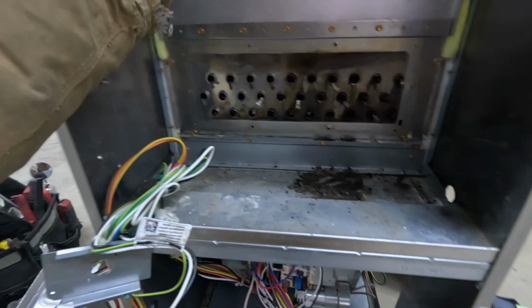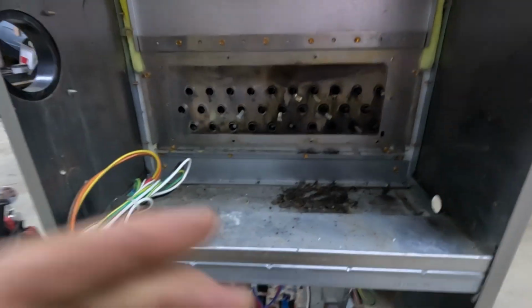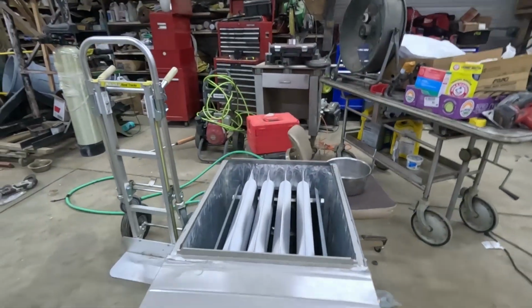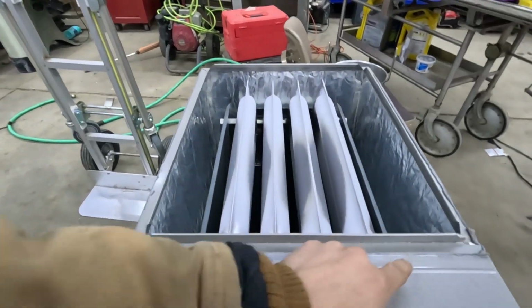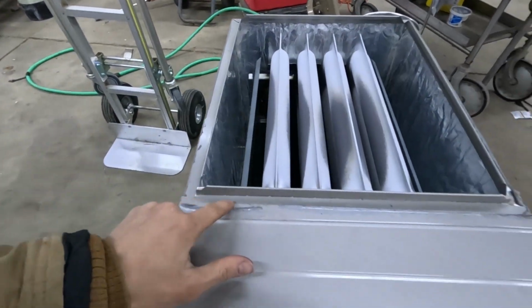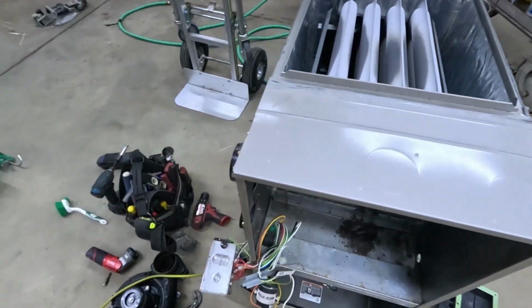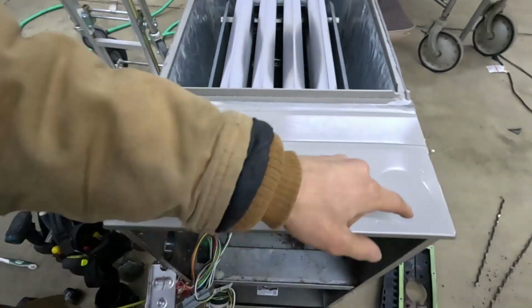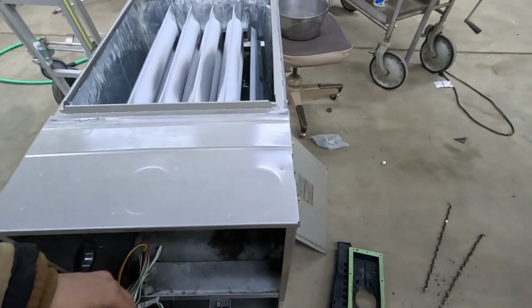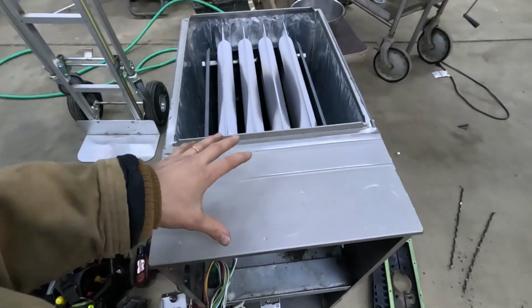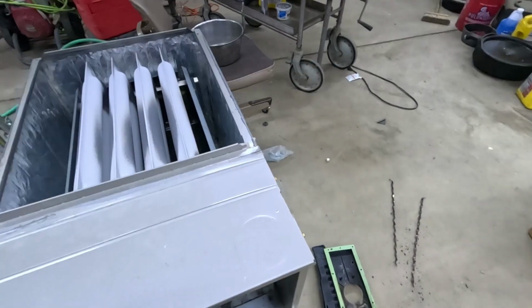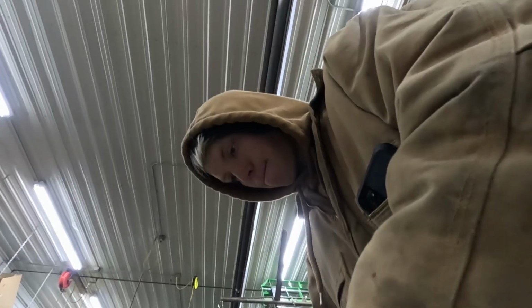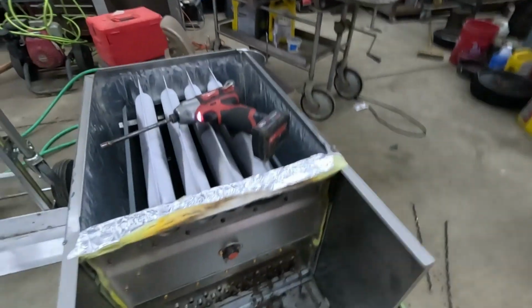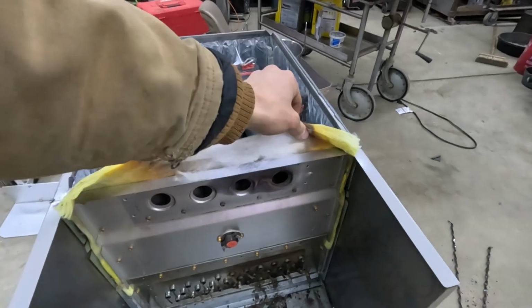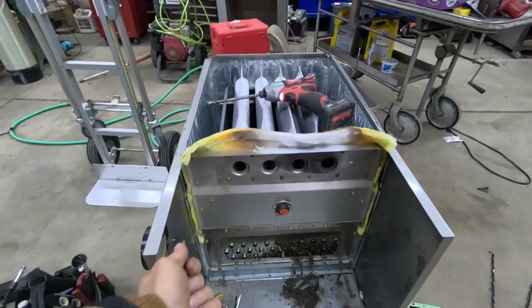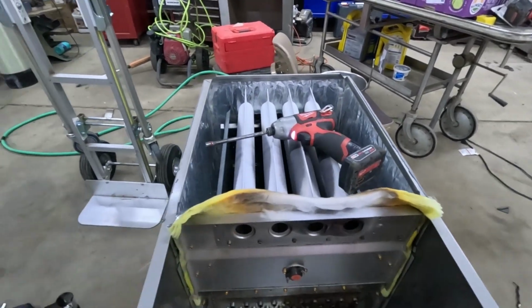We're ready to start removing the screws that actually hold this piece in. Now, depending on your ductwork might infringe on this. You can see the ductwork on this one was siliconed right here, but usually you can just take out these couple of screws and kind of pry this up a little bit to give yourself a little extra clearance. I'm going to have the luxury of just taking it completely off, so I'll probably just do that here. That'll just give us a little more space for sliding this piece out. But if you do have to just flex it up at the end, it's really not that big a deal.